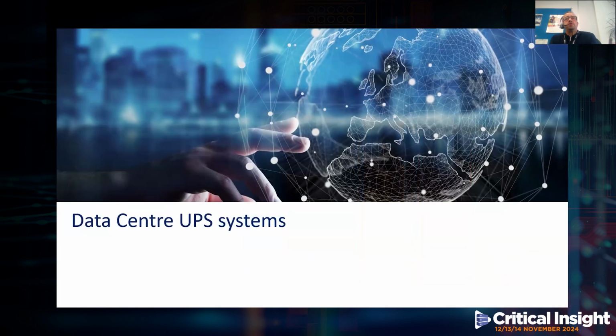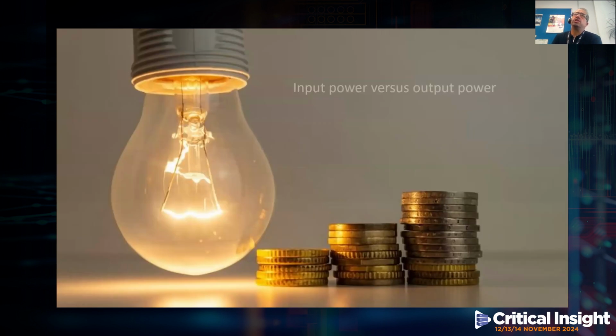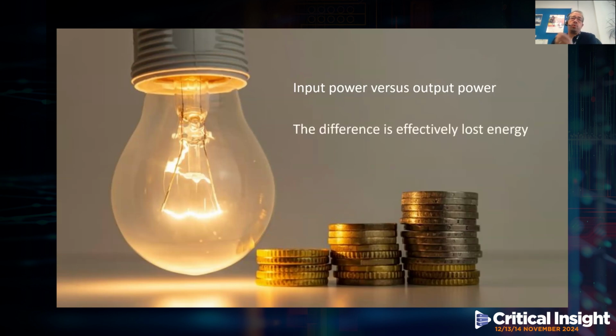Now, when we talk about operational energy, the most critical figure within any UPS is the overall system efficiency, as it affects so many different areas. By definition, the UPS's efficiency is defined as the active power measured at the input versus the active power measured at the output, which is typically measured in watts, kilowatts, or even megawatts, depending on the size of the system. The difference between the input and output power is effectively lost energy, which is typically wasted. In most cases, this wasted energy is converted to heat, which generally needs to be removed or cooled, which again requires more energy. So it's a vicious circle.